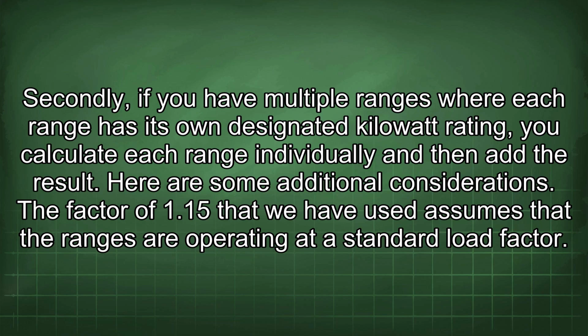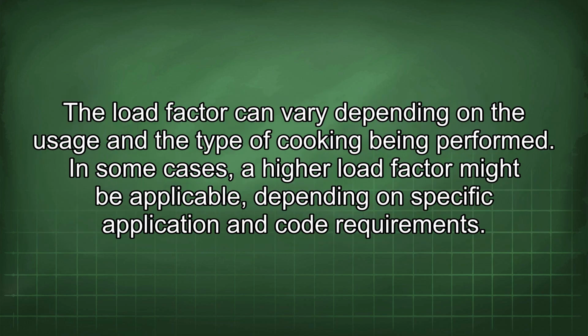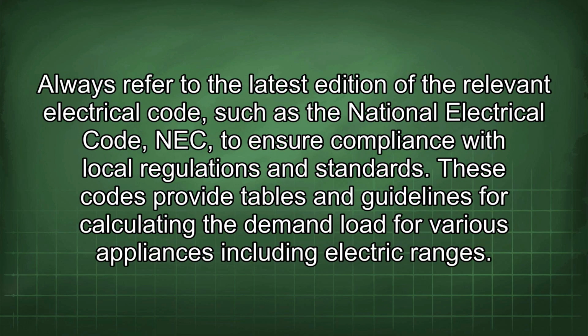The factor of 1.15 that we have used assumes that the ranges are operating at a standard load factor. The load factor can vary depending on the usage and the type of cooking being performed. In some cases, a higher load factor might be applicable depending on specific application and code requirements. Always refer to the latest edition of the relevant electrical code, such as the National Electrical Code (NEC), to ensure compliance with local regulations and standards. These codes provide tables and guidelines for calculating the demand load for various appliances, including electric ranges.